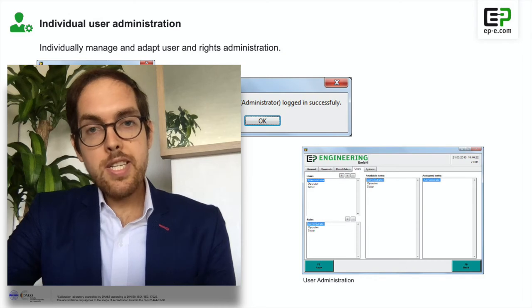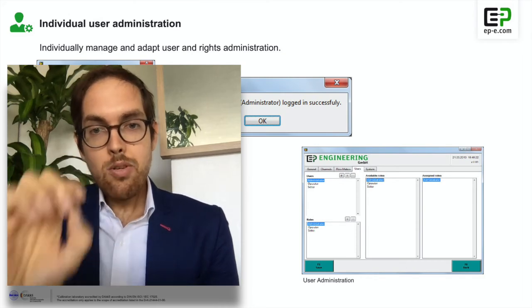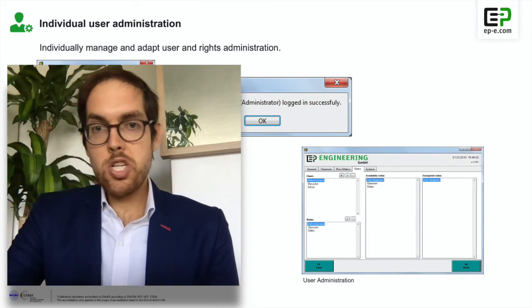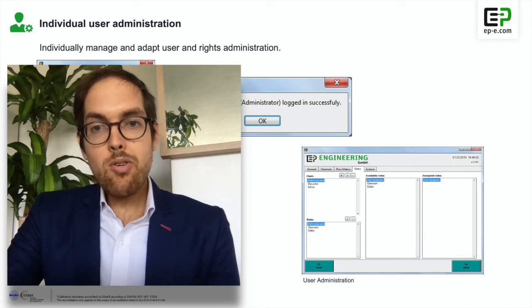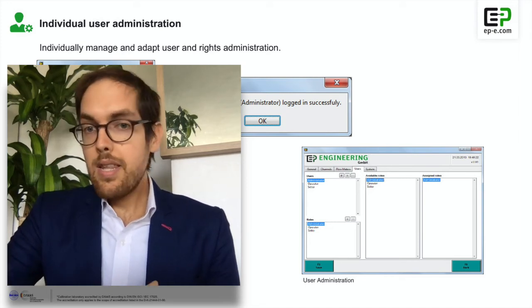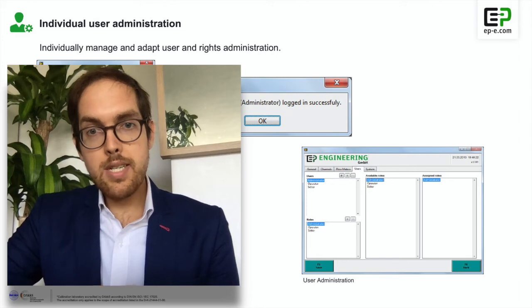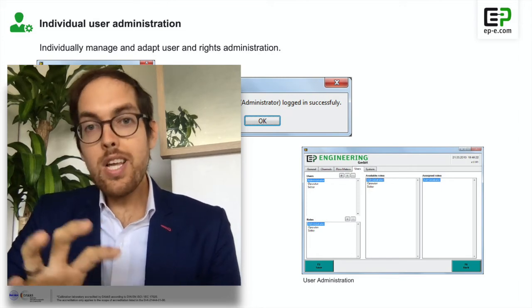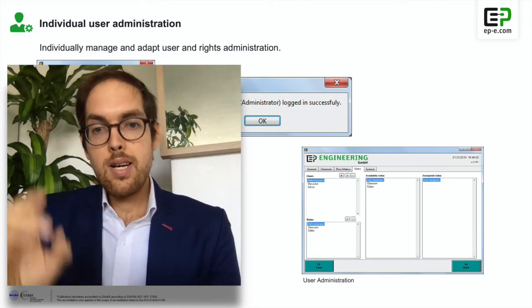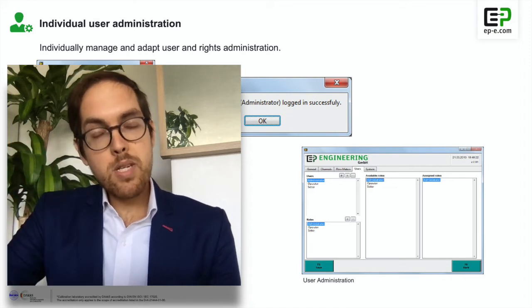What I want to mention here is the user should never be able to change the calibration data, because he could do it by accident. Then you have for 7 months a system which is measuring totally wrong and you don't notice it because someone changed the parameters.